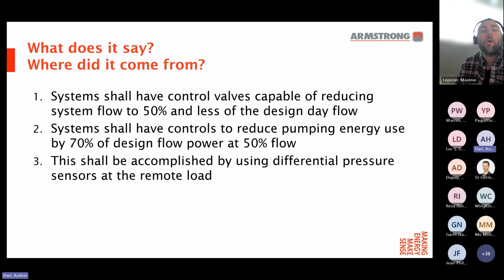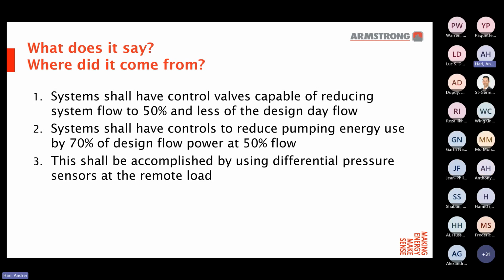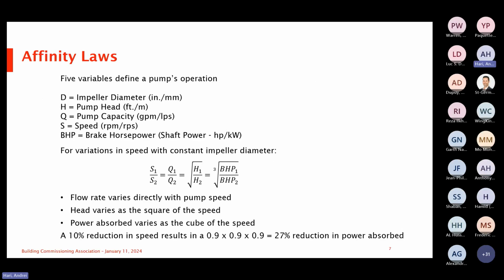When we reduce that flow by 50%, the energy being consumed is reduced by 70%. And this is being done by using a differential pressure sensor or some other control device that is located or mimics the most hydraulically remote load in the system. And so I always ask, when I'm doing my lunch and learns, where did ASHRAE come up with this? And quite simply, all of this is based on fluid dynamics and specifically the affinity laws.